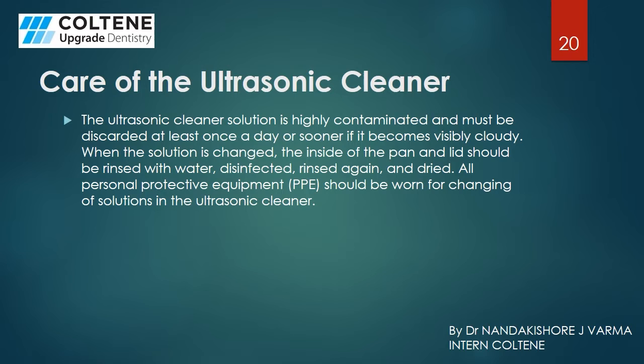Like every equipment, let's see how we should take care of an ultrasonic cleaner for its long life. The ultrasonic cleaner solution is highly contaminated and must be discarded at least once a day or sooner if it becomes visibly cloudy. When the solution is changed, the inside of the pan and the lid should be rinsed with water, disinfected, rinsed again and dried. All personal protective equipment should be worn for changing of solution in the ultrasonic cleaner.